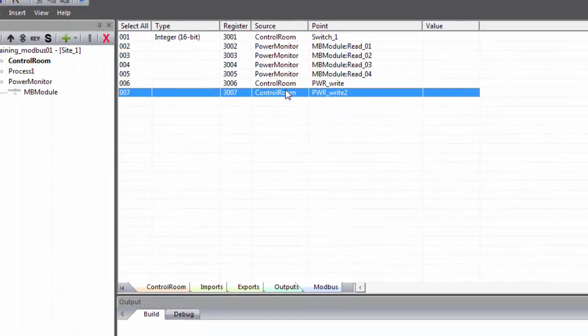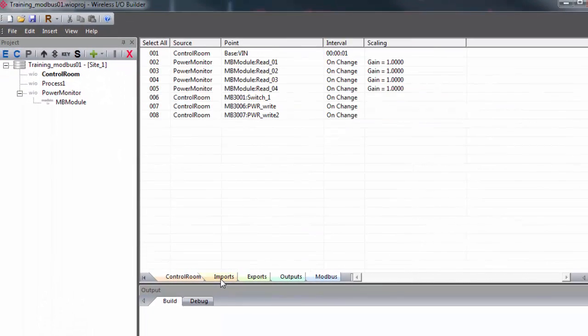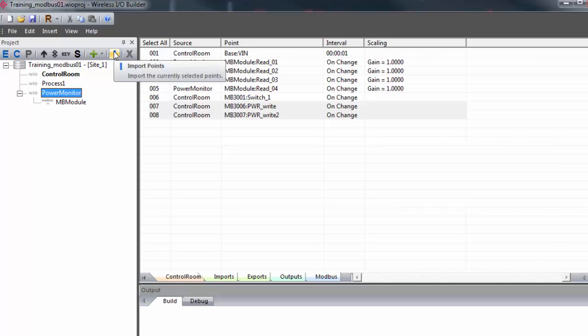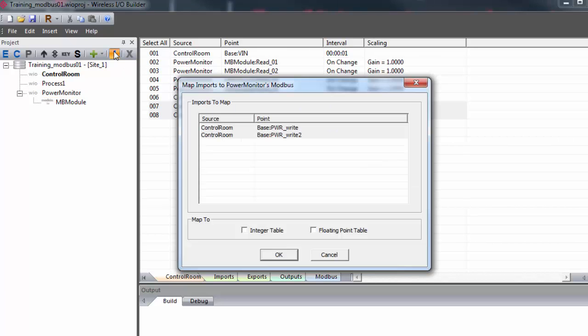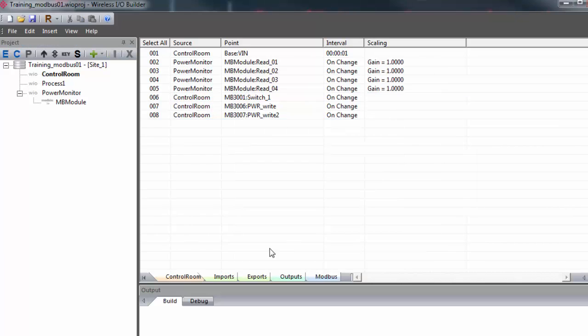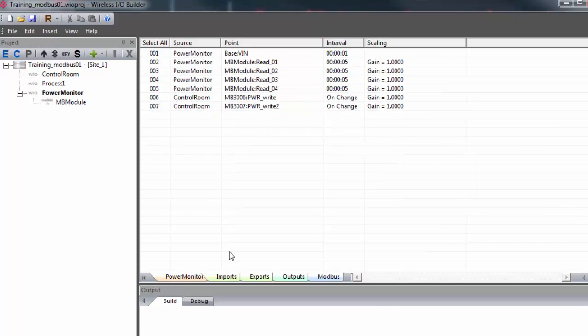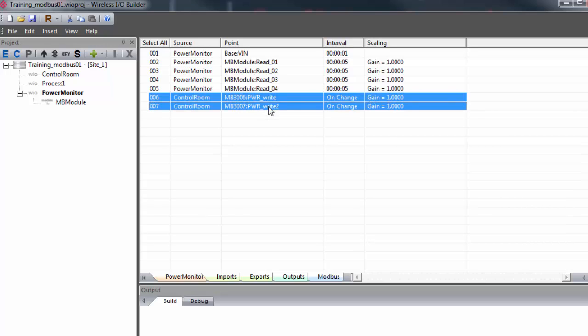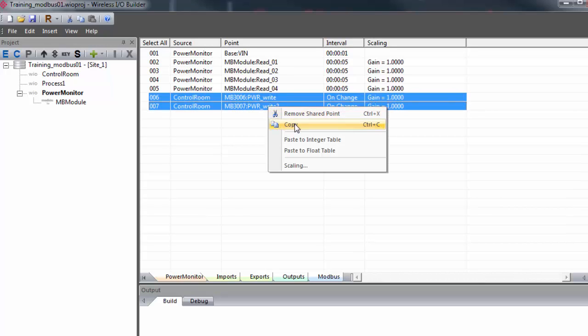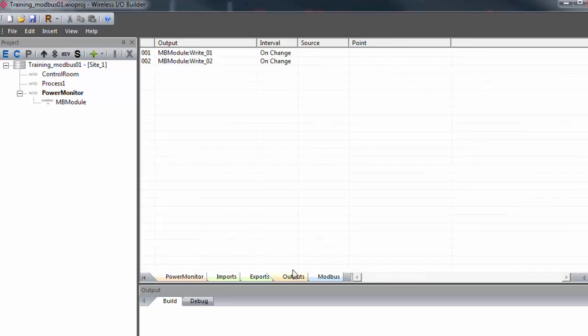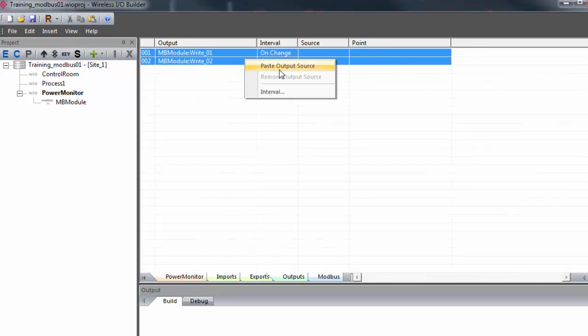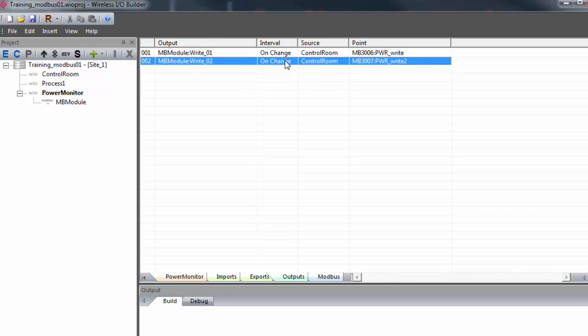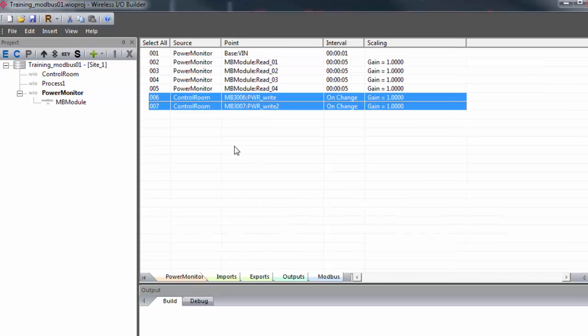Then go to the imports tab, select our newly minted write commands, single click on the power monitor and hit the import button. We'll paste the points to the integer table. Then we'll select the power monitor and we'll select the write commands in the import tab. Copy, go to the outputs tab, select the output points from our Modbus device and paste the output source. So now values written to these registers in the power monitor gateway will be pushed into the specified addresses of the Modbus slave.